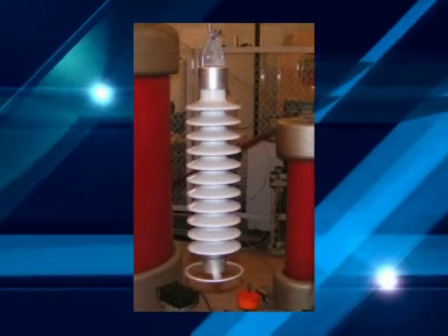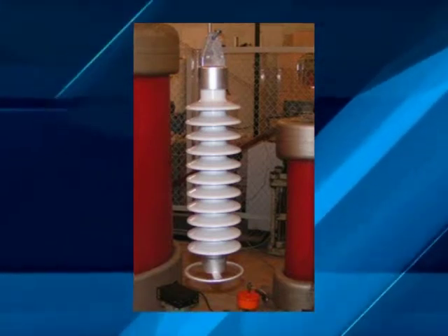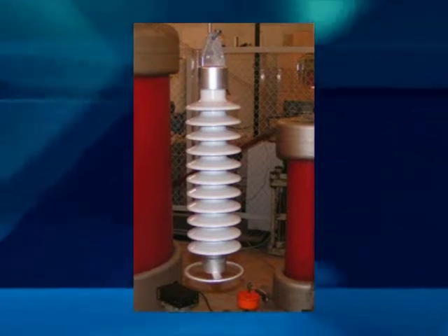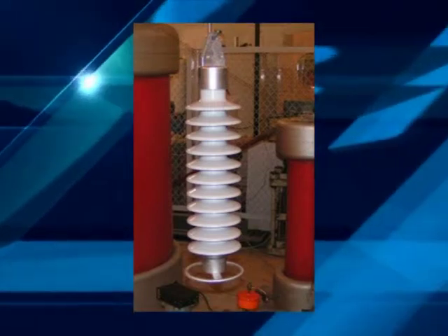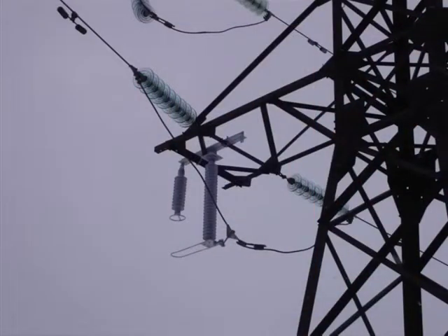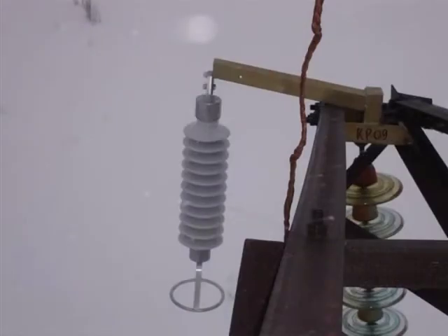Under the effects of lightning surges, which threaten line insulation, the air gap of the arrestor is breached, connecting the working resistor to the wire. Under the effects of voltage with industrial frequency, the current through the working resistor is limited to the values at which the existence of the arc in the spark gap becomes impossible. Arrestor of type RVL on 110 kV overhead lines, Aleshinskaya and Pimskova oil field. This is one of the most important oil-producing companies in Siberia, on the intermediate tower, on the anchor tower.